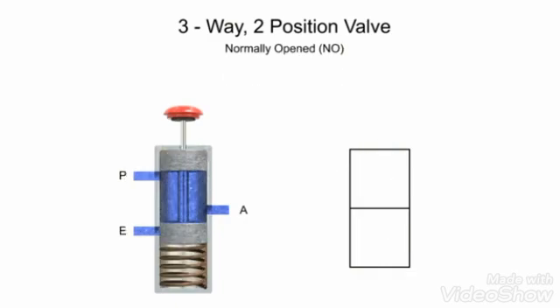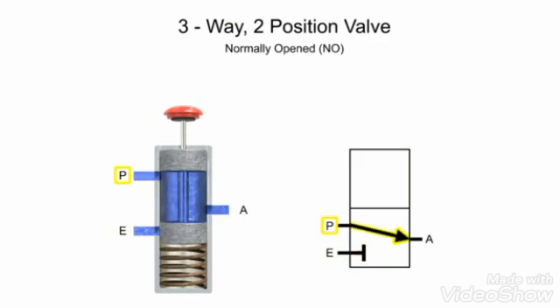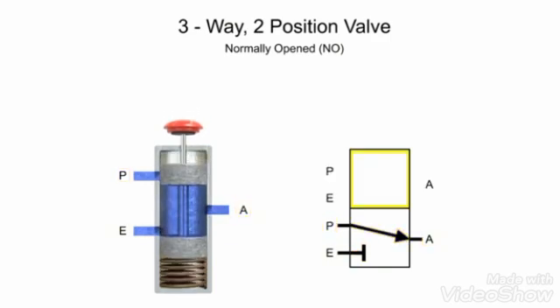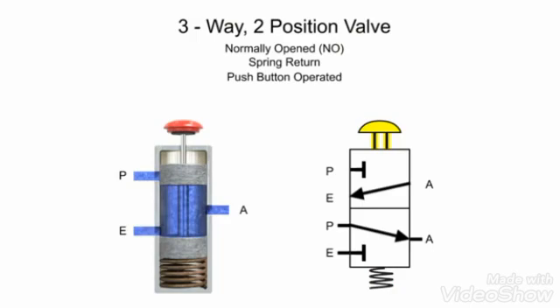Here is another three-way, two-position valve. This valve also has an inlet port P, exhaust port E, and output port A, but they are in a different configuration. In its normal position, exhaust port E is blocked and fluid flows from pressure port P to outlet port A. In the second position, pressure port P is blocked and allows fluid to flow from outlet port A to exhaust port E. The valve is also spring return and push button operated.